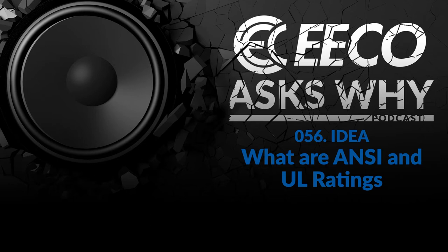So thank you. Exactly. There's a pretty cool thing that I went through when I used to help manufacture and design switchgear for their arc resistant arc flash gear, where they would actually hold cotton sheets up about 2 inches away from a piece of equipment, and they would blow the equipment up, and they would test to see if there was any kind of char marks on those cotton sheets. If there was, it would fail the UL test. So that was kind of cool, and brings back to your point all about safety and containing the arc blast in that regard.